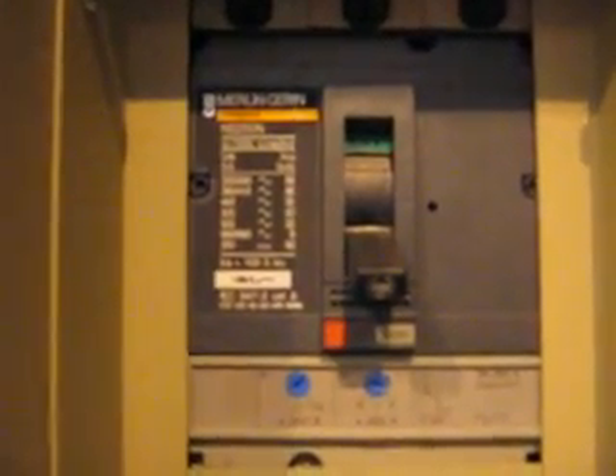This is a molded case circuit breaker, and this particular one is a 250 amp. It has both adjustable thermal and magnetic settings. The thermal settings are overload, the magnetic settings are short circuit, and at the moment it's set for overload at ×1, in other words it's a 250 amp breaker, and the magnetic settings are on ×10, so it will trip instantaneously at 10 times 250, which is 2,500 amps. That's the main MCCB, and here are the circuit MCBs, distribution circuits, presumably feeding distribution boards. These lower ones are single phase. They're not adjustable in any way.